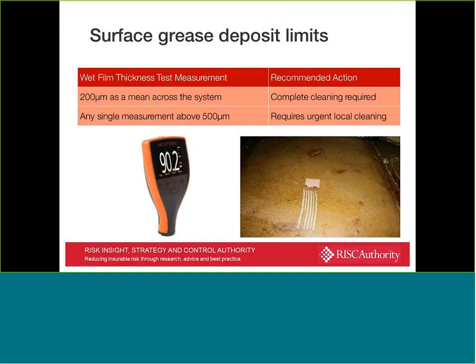The TR19 indicates requirements in terms of when does a system need cleaning. I've just shown a couple of devices, one quite techy and one quite manual, which are used to measure wet film thicknesses. But in general terms, 200 microns measured as a mean across the system would indicate the complete cleaning is required of the entire system, and any single measurement above 500 microns would suggest that urgent local cleaning is going to be necessary.